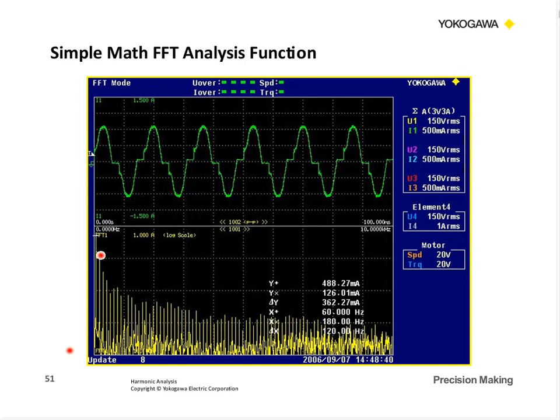Now, if we're measuring up here the amplitude on these high harmonics, we can measure those just fine with our scope or this simple math function. But if we're trying to do a total harmonic distortion, which includes all these harmonics, it's going to be difficult to do. They're not going to be able to do it very well with all these false harmonics or bleed down here.